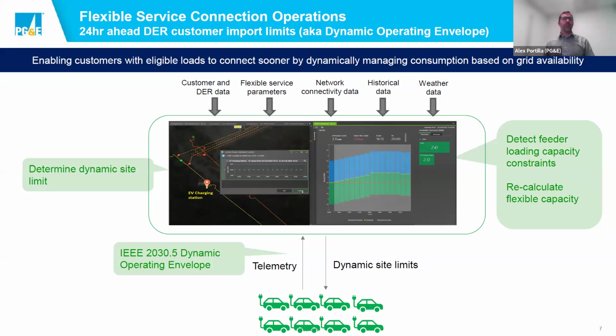Customers with flexible loads, whether the demand itself is flexible or they have local generation or storage providing that flexibility, need to receive that day-ahead hourly limit signal and translate it into a local control action. For example, a charge station with 50 chargers needing to cut back to 50% of demand could feather the charging, reduce output on half the chargers, or reduce all chargers by 50%. It's up to the customer to determine what control action to take.